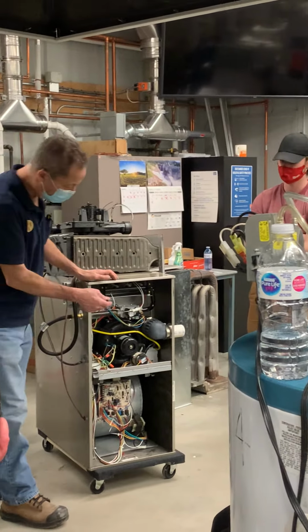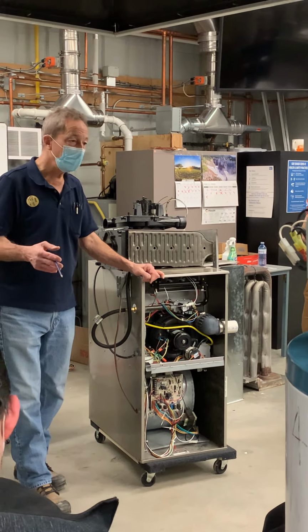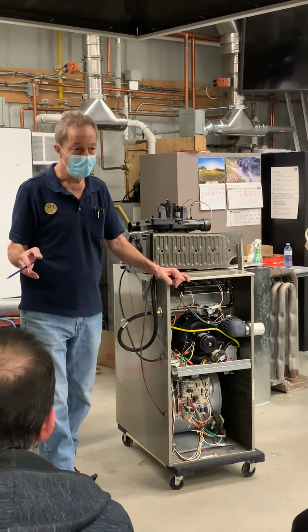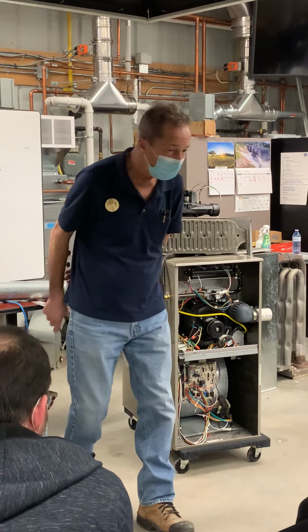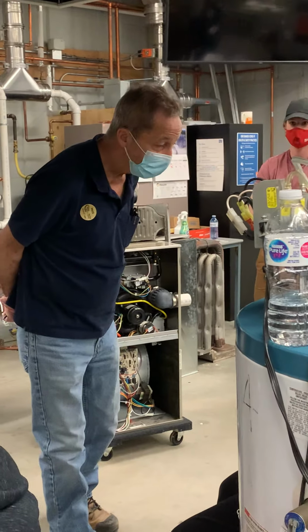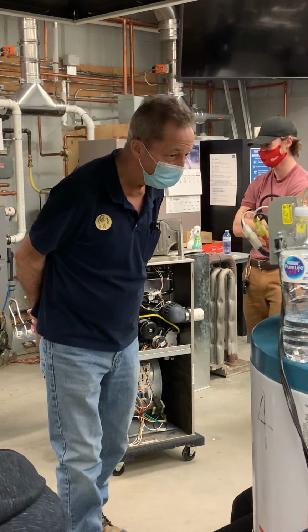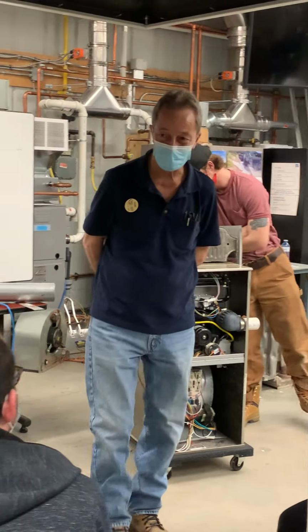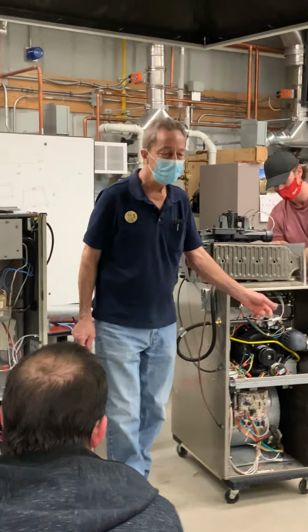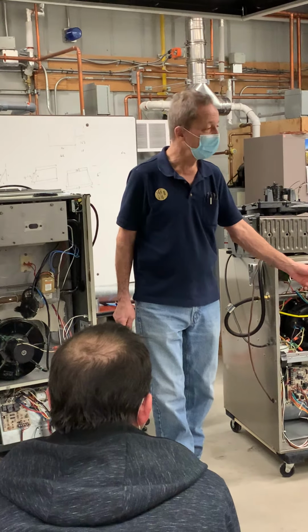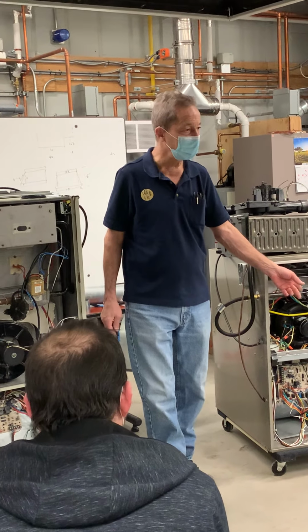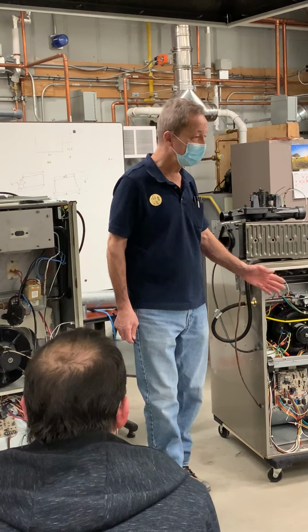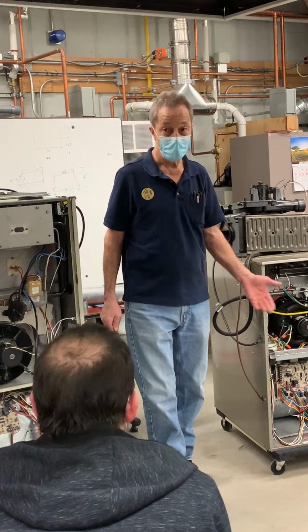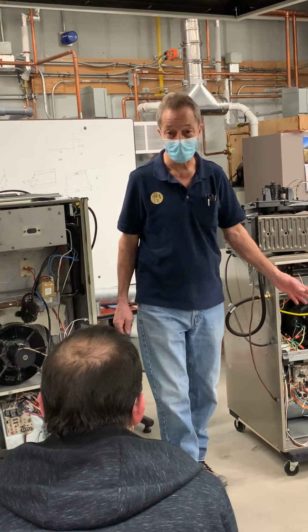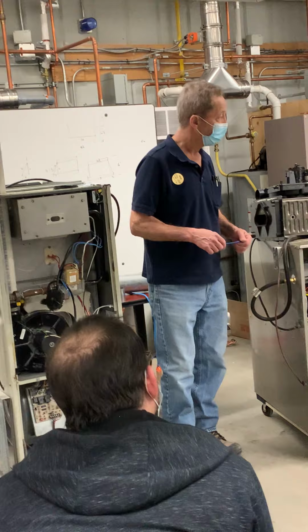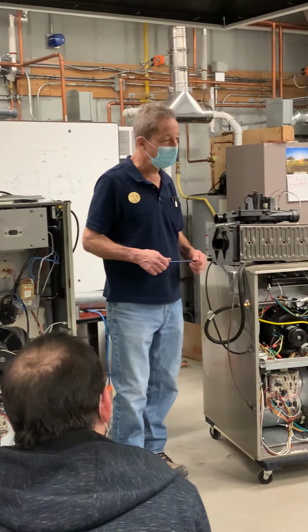So if you hook up to this appliance and you see that it's sucking -3.5 or -4, what are you thinking? Yeah, but why is it sucking too hard? Because it's a blocked secondary heat exchanger. So if you get a flame rollout, check with your digital manometer, check the pressure that the inducer is doing. If you see it sucking to -3.5 to -4, it's a blocked secondary heat exchanger. That's why the flame rollout's tripped. And then what do you do? Put a new secondary heat exchanger in or change the furnace.